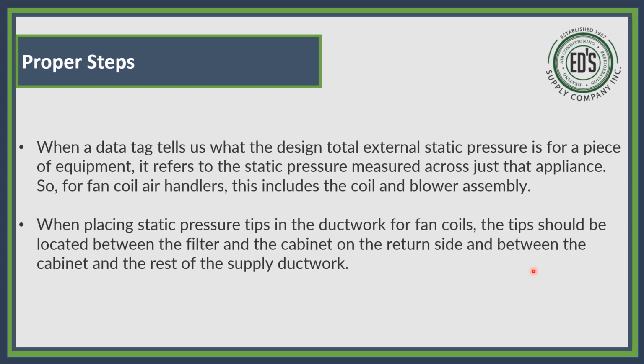When placing static pressure tips in the ductwork for fan coils, the tips should be located between the filter and the cabinet on the return side. That means after the filter, before the cabinet, or in the cabinet before the blower motor, and between the cabinet and the rest of the supply duct. Some of the contractors now put a 3 or 4-inch piece of metal between the furnace and the A coil, and that is so they can measure the static pressure. Now, let's say the manufacturer says it's certified at 0.2 in heat. That is from the return before the coil. And that's where you need to make sure that thing is set to get the optimal CFM that the motor's blowing out.